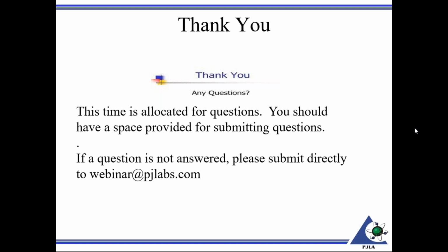Under the decision rule, how is it communicated to the customer? I believe that was part of that question. Like I stated, during the contract review process, the customer has to be made aware of and agree to the decision rule. So that could be as simple as a quote, or perhaps a contract if it's something long term, explaining the decision rule. Again, this is when you're making a statement that complies: pass, fail, in tolerance, out of tolerance.